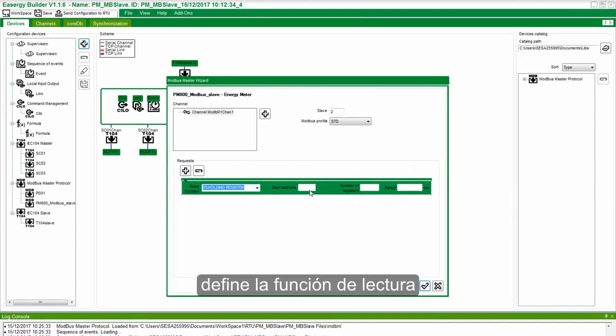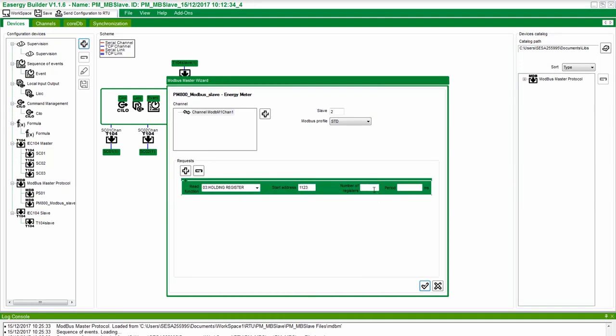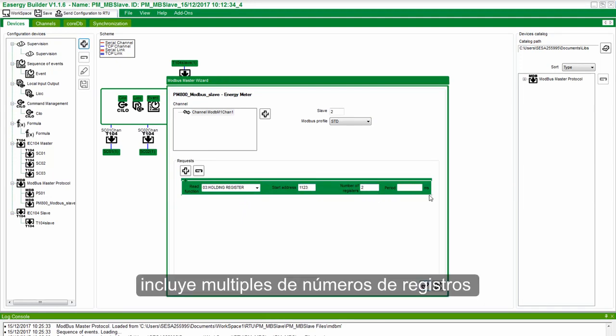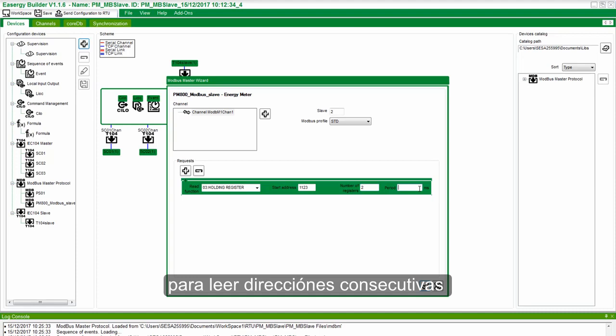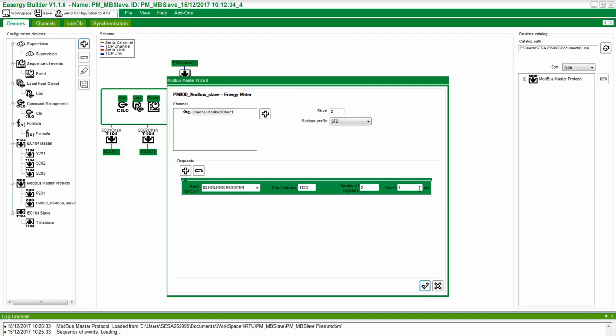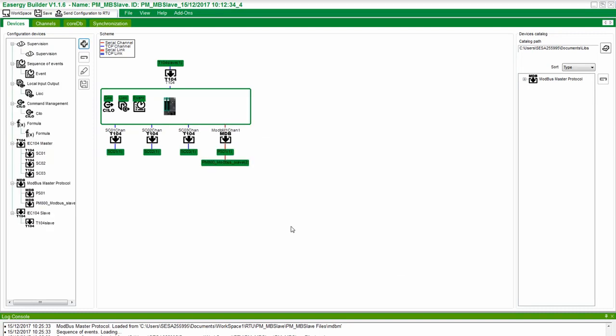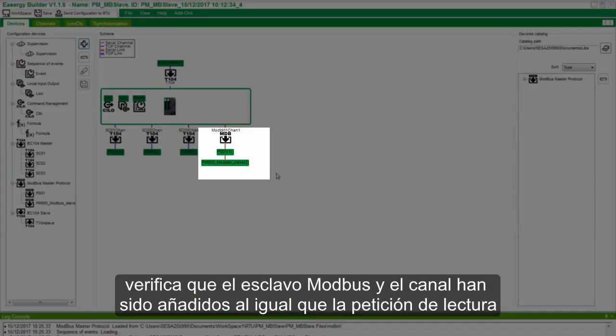Define the Read function Start Address, Number of Registers, and Period. Include multiple registers to read consecutive addresses. Click on the checkbox when done. Verify that the Modbus Slave Device and the channel have been added along with the Read Request.